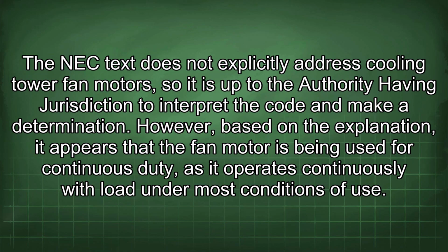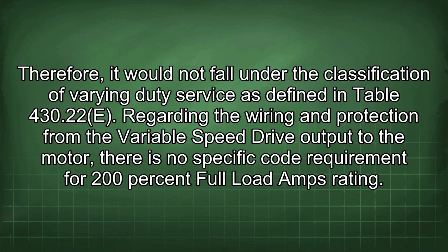The NEC text does not explicitly address cooling tower fan motors, so it is up to the authority having jurisdiction to interpret the code and make a determination. However, based on the explanation, it appears that the fan motor is being used for continuous duty as it operates continuously with load under most conditions of use.